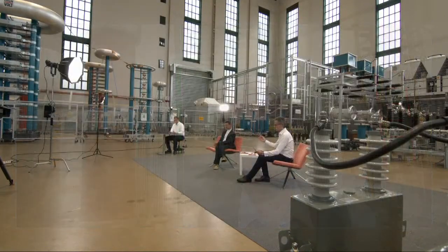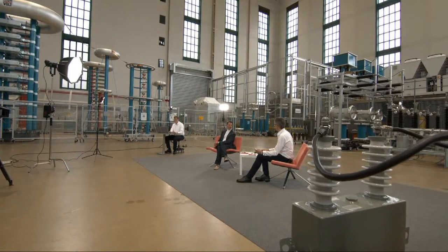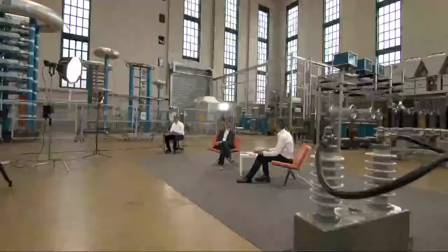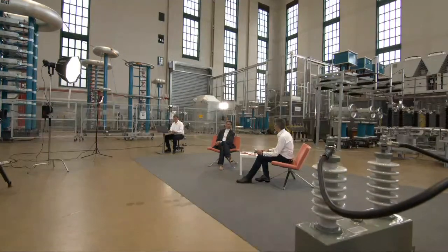Okay, system integration tests of components—Alex? I gave the example already with the cables. A lot of cable systems consist of joints connecting cable parts together into one cable system, and these joints can only be tested at site, since they were not assembled in advance. So it's absolutely mandatory to make these on-site tests, and this is a complete system test.